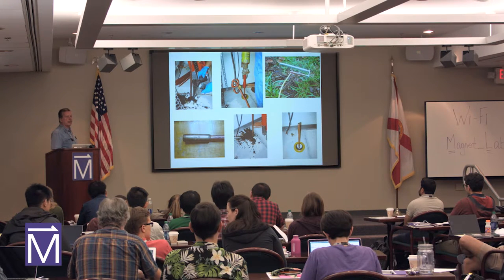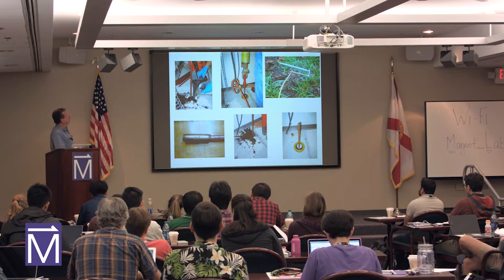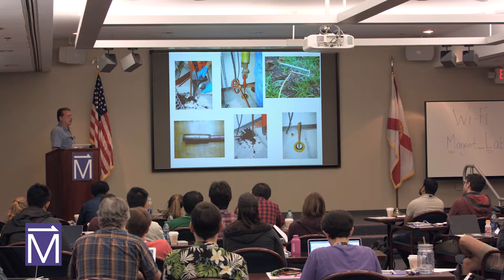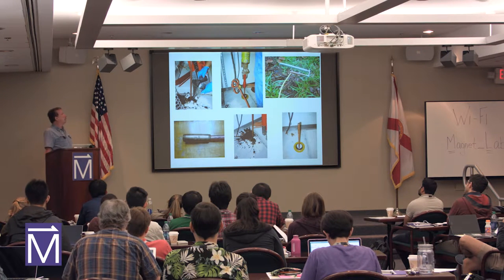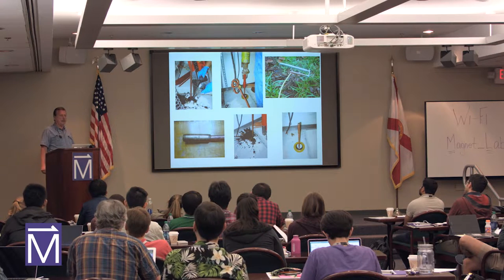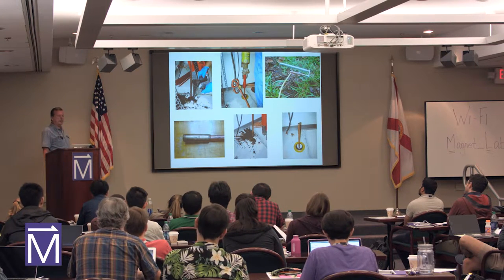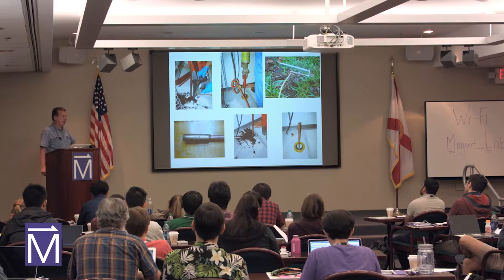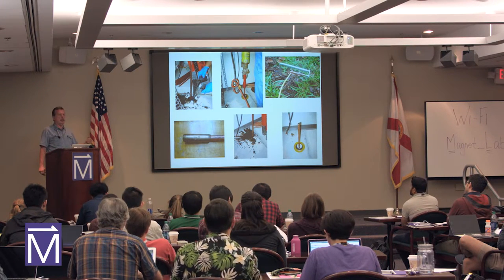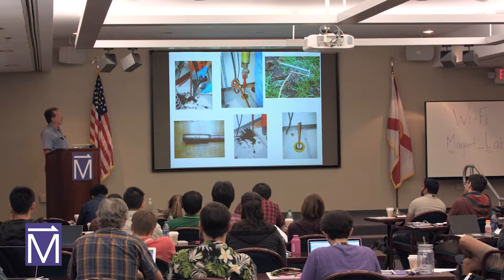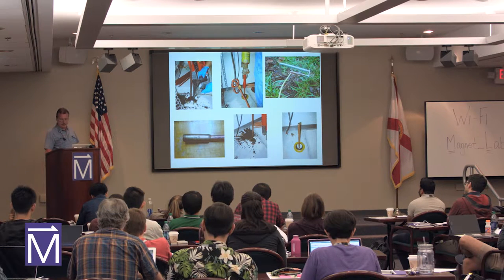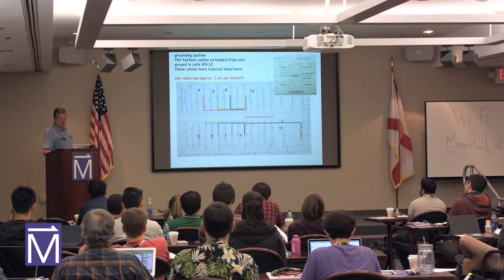Another method is with our clamp-on ground measurement. So if you have grounding rods under investigation and something you know is a good ground, you use this clamp-on device, which basically works as follows. It puts a pulse of, I think, 3 kilohertz magnetic field or current into this loop, and then measures the answer. And it's sort of calibrated. We compared those methods, and they agreed very, very well.